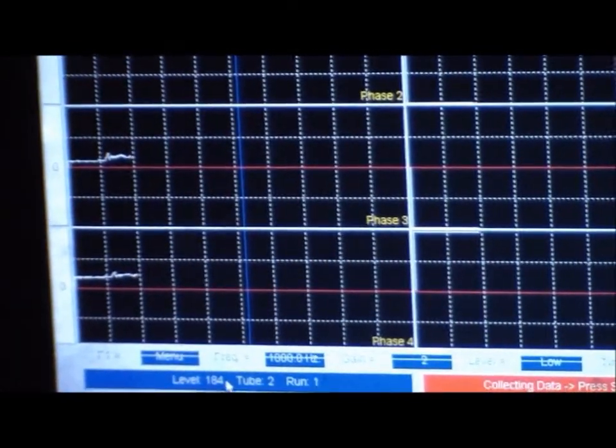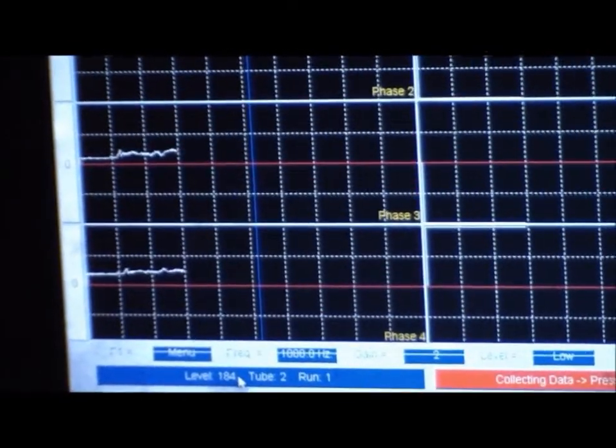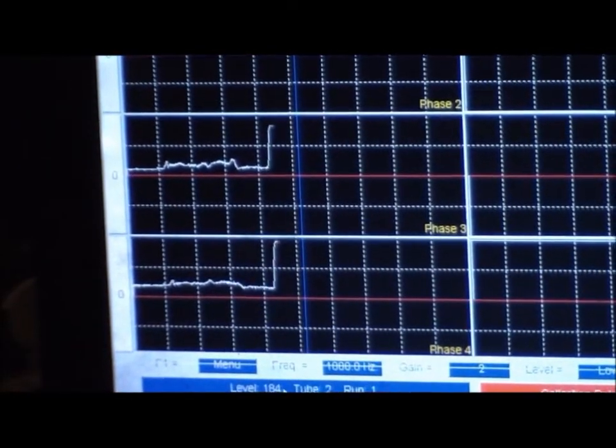When wall loss is encountered, the response increases, and when additional metal is present, like a magnetite deposit, the signal decreases.